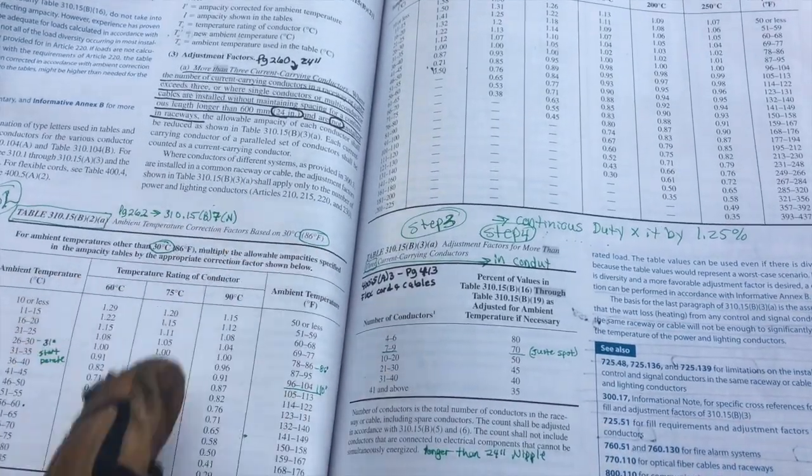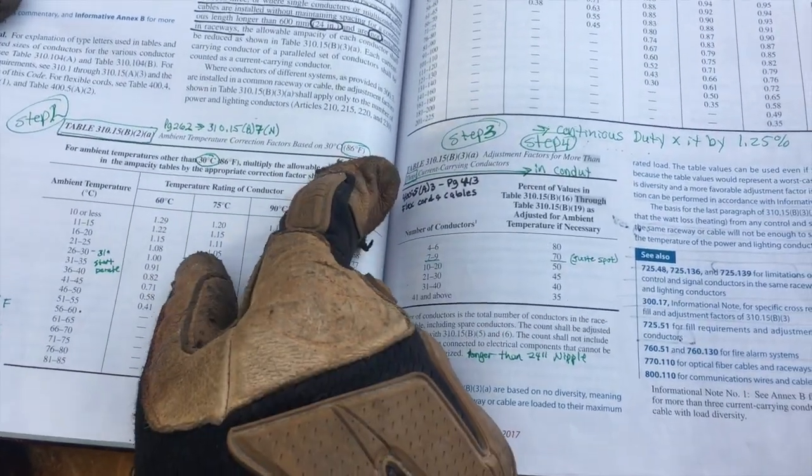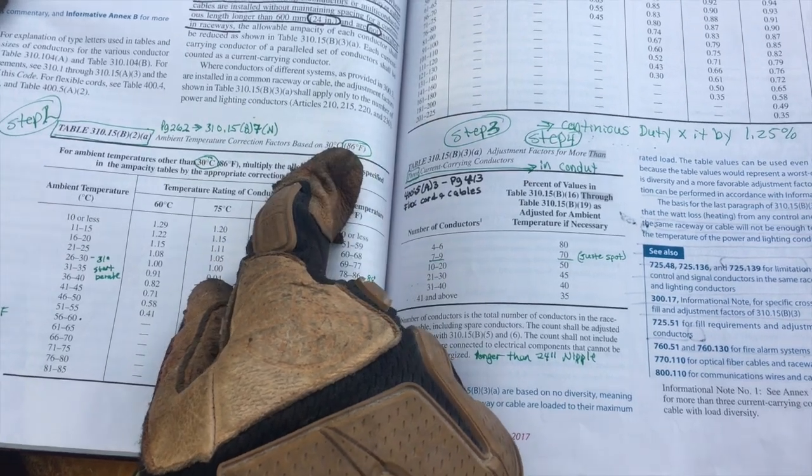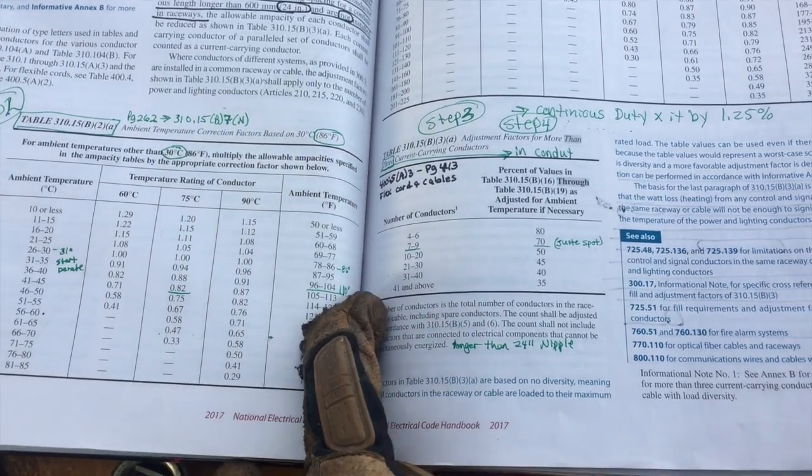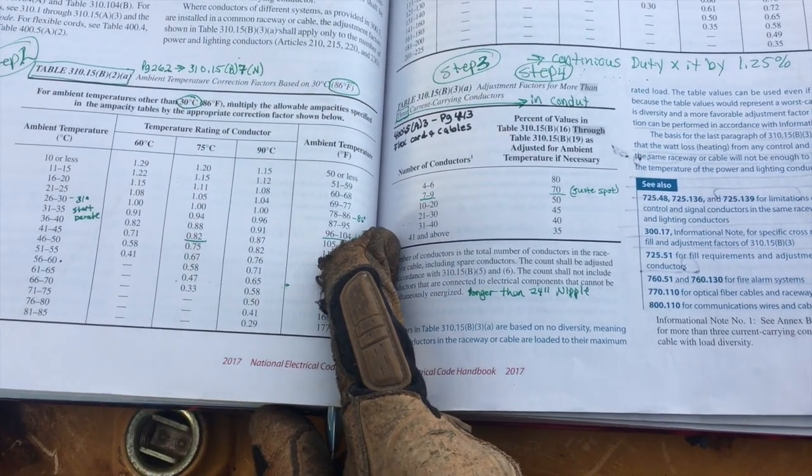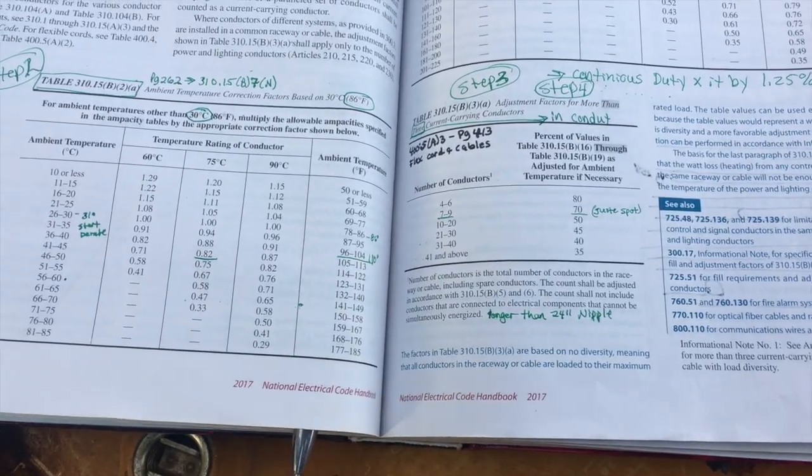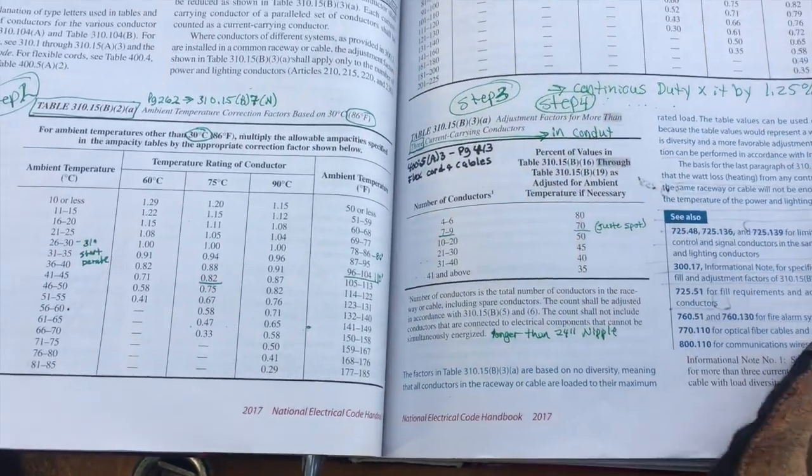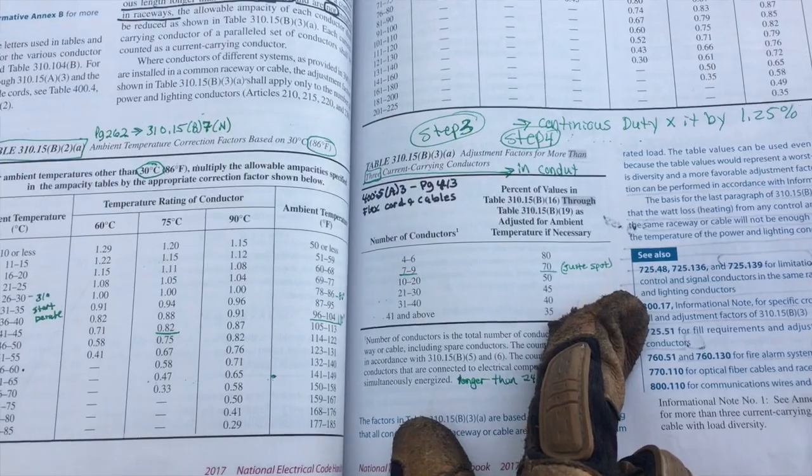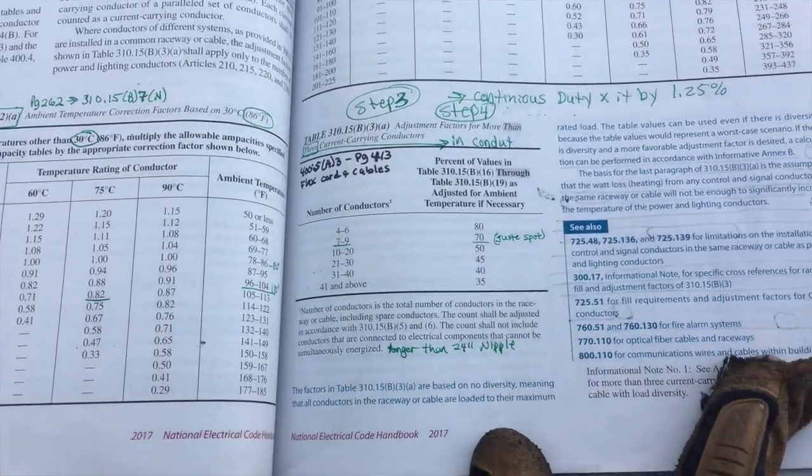Your ambient temperature rating, if you're 30 to 86 degrees Fahrenheit, 30 degrees Celsius, 86 degrees Fahrenheit, as soon as you get to about 100 degrees in Colorado, then you'd be concerned. You also look at how many current carrying conductors are in a conduit like I told you, that ties to 400.5.